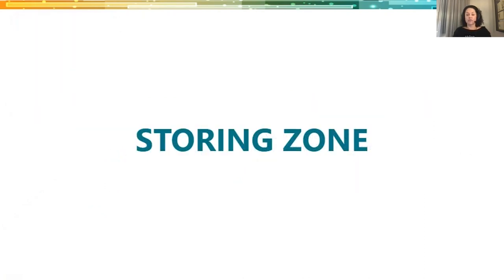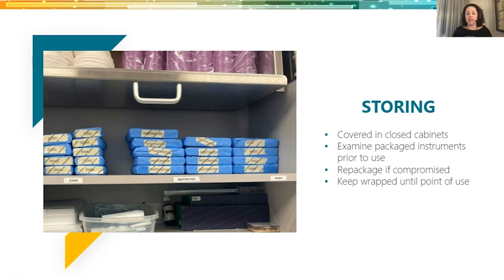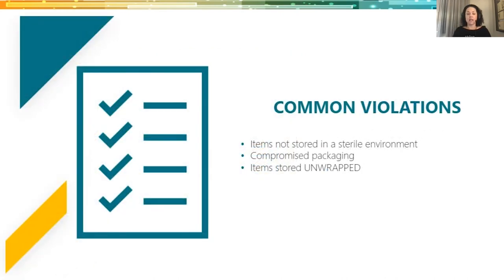Zone four is the storing zone. You must place everything in covered, closed cabinets. Examine packaged instruments prior to use, repackage if compromised, and keep wrapped until the point of use. Common violations: items not stored in a sterile environment; compromised packaging still in rotation for use on patients; and items being stored unwrapped — like XCPs loose in a drawer, which is a definite violation.